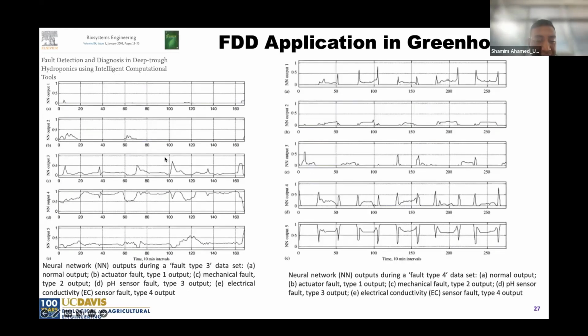This is for the pH sensor. In this case, this is the normal operation, but if you look at the fourth graph, you see a different signal from the control system, giving an indication of faulty operation of the pH sensor. The last graph shows fault detection for the electrical conductivity sensor.